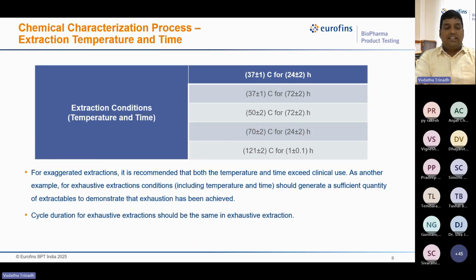Then coming to extraction conditions in terms of temperature and time. Basically, there are different types of extraction conditions as per the guidelines, which are 37 degrees plus or minus 2 for 24 hours, 37 degrees plus or minus 2 for 72 hours, 50 degrees plus or minus 2 for 72 hours, 70 degrees plus or minus 2 for 24 hours, and 121 degrees plus or minus 2 for 1 hour.